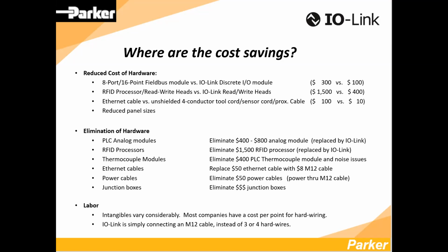As for analog, I'll touch on that in a second. But as far as networking and power cables, these are expensive because they're not on the fieldbus. Now you're connecting with a 4 or 5 conductor unshielded cable—tool cord, sensor cord, prox cord, whatever you call it—maybe $10, as opposed to $100 for an Ethernet or Profinet M12 or RJ45 cable. You're saving money there as well.